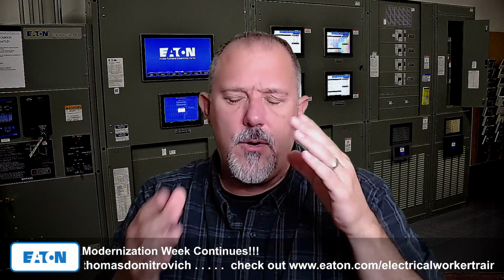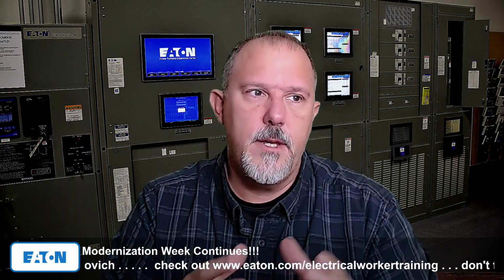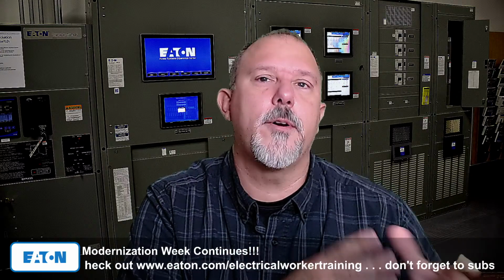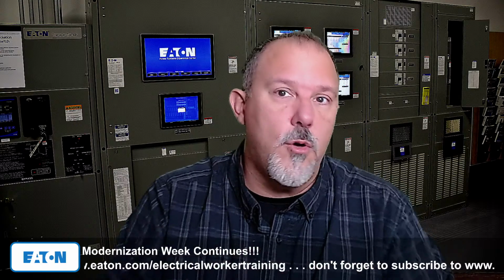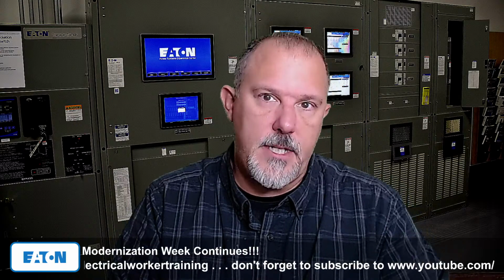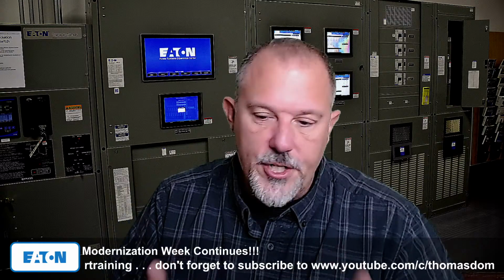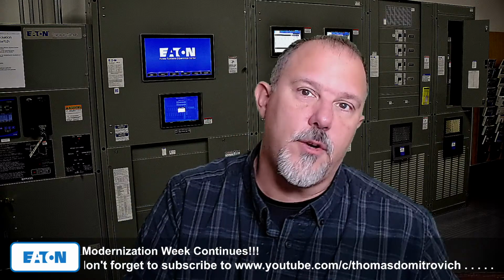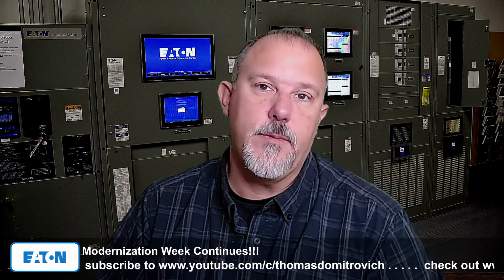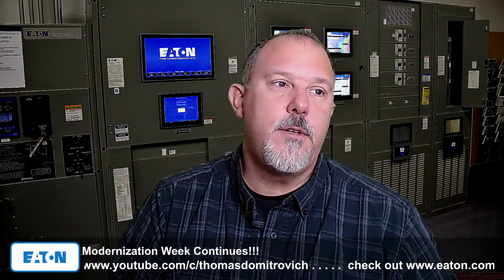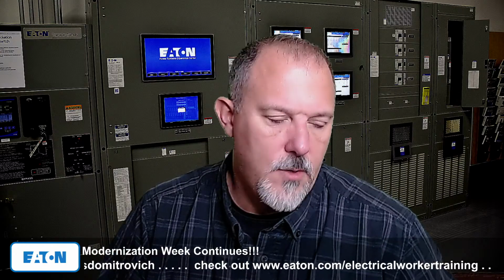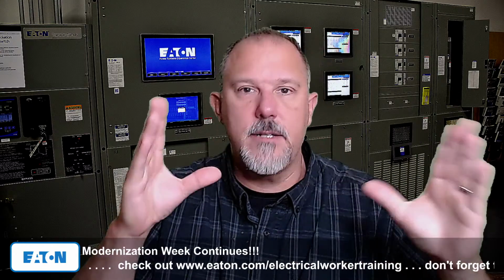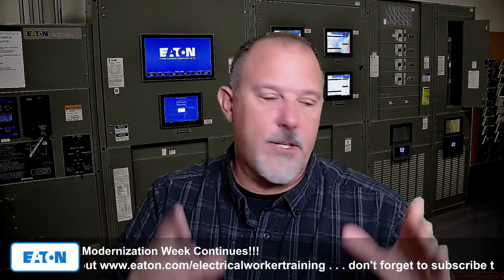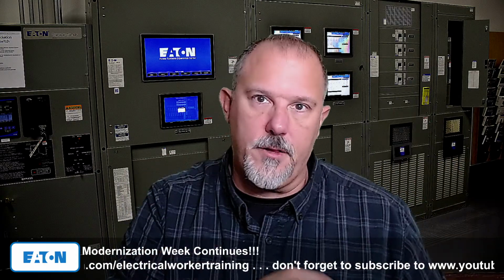Now, you've got to remember how the meter works. I've got over 10 milliamps flowing on this equipment grounding conductor. And it's looking at multiple frequencies, right? 60 hertz and up. And the question that the standards people are trying to address is, will the higher frequencies kill you? Now, Dalziel did study across a spectrum, up to 10 kilohertz, I can't remember the number. And I'll tell you that this one and others violate that.